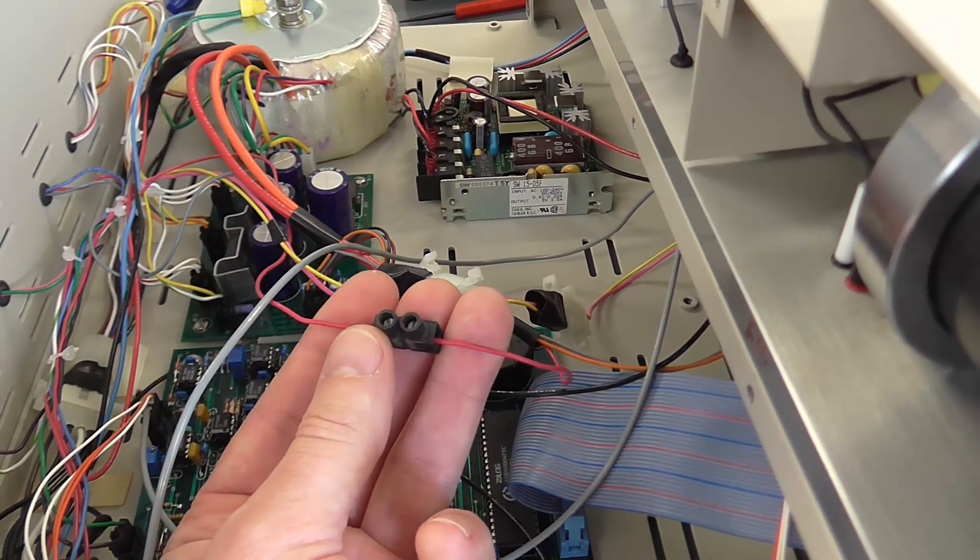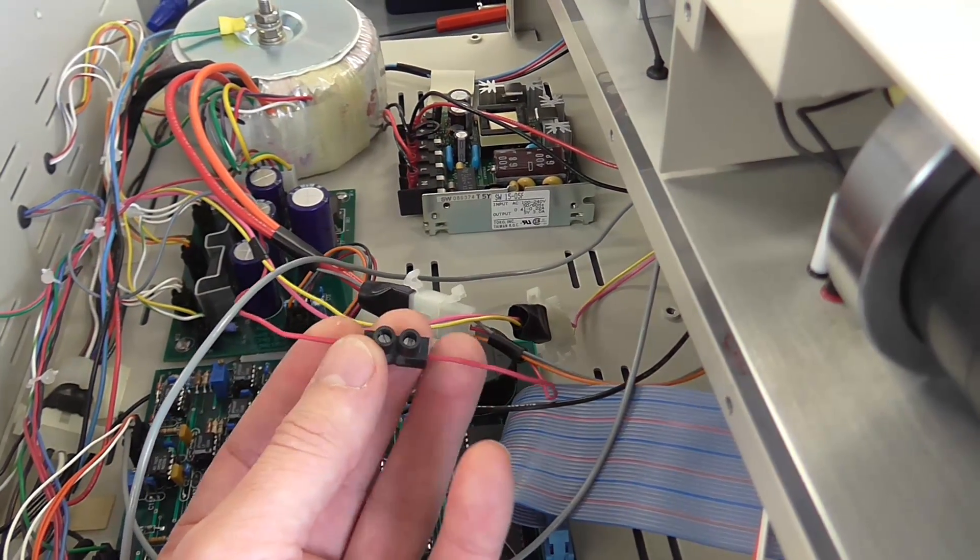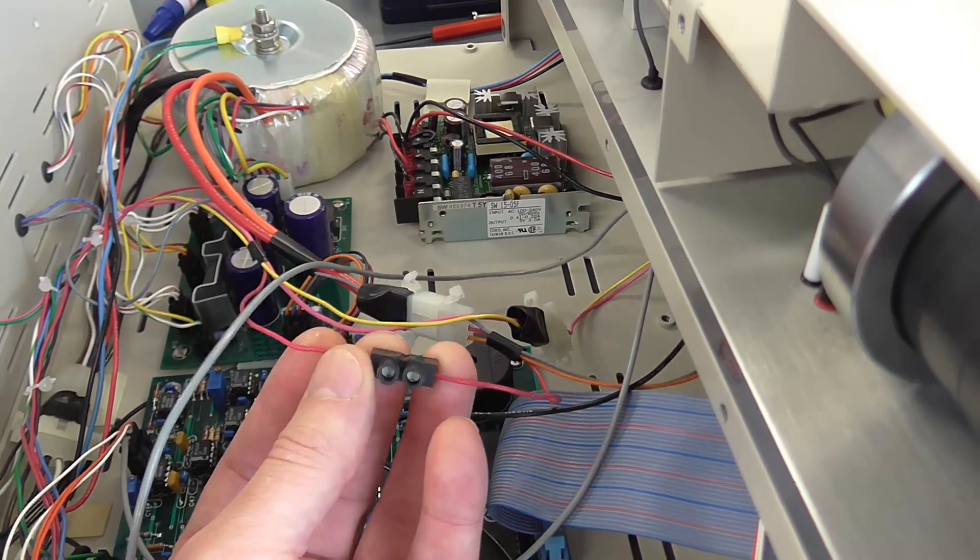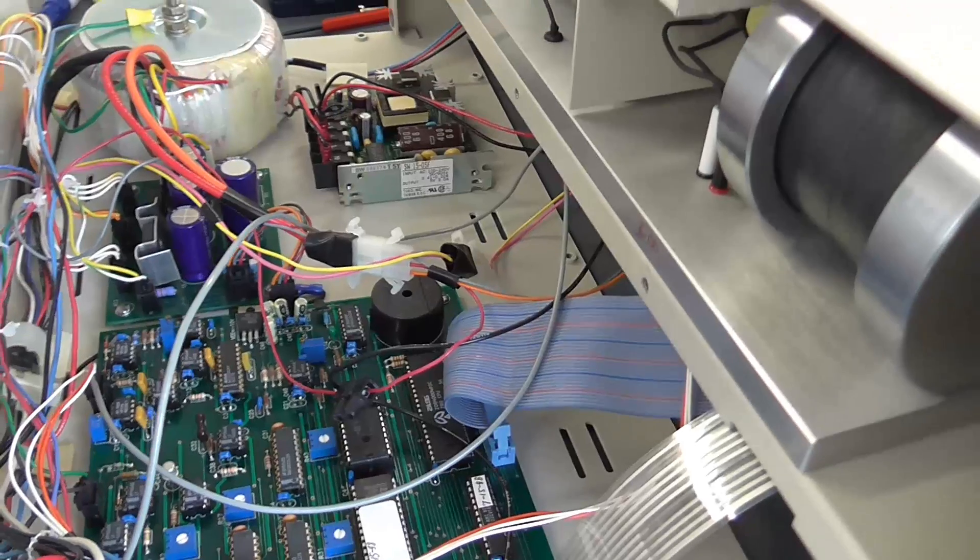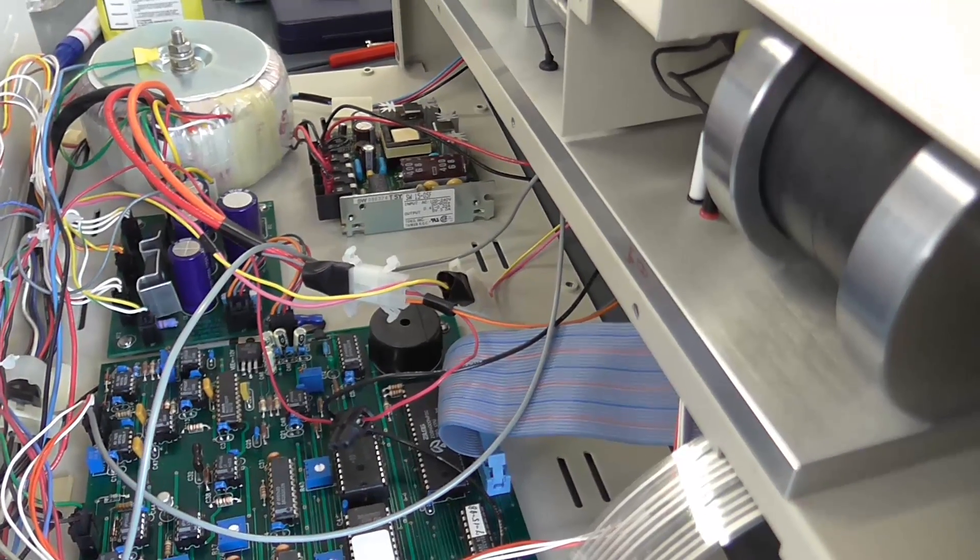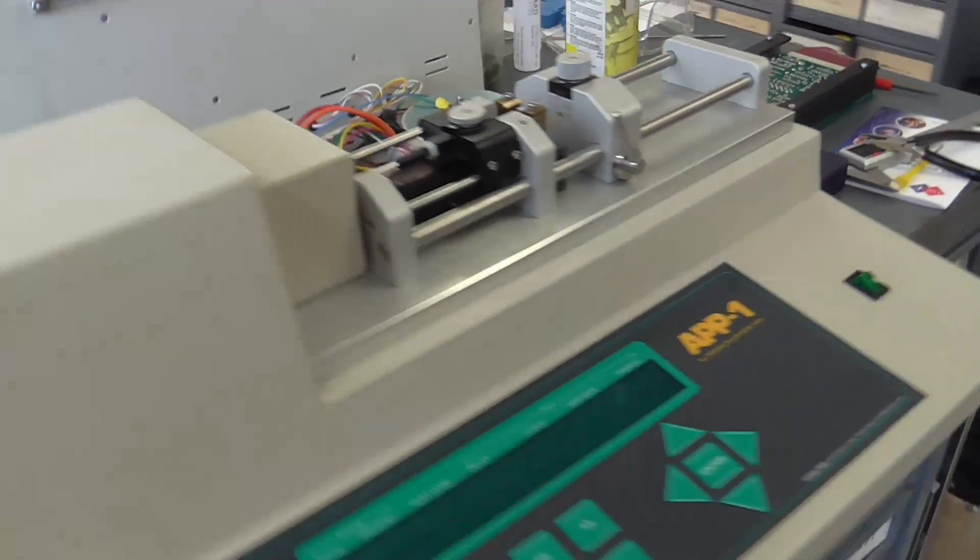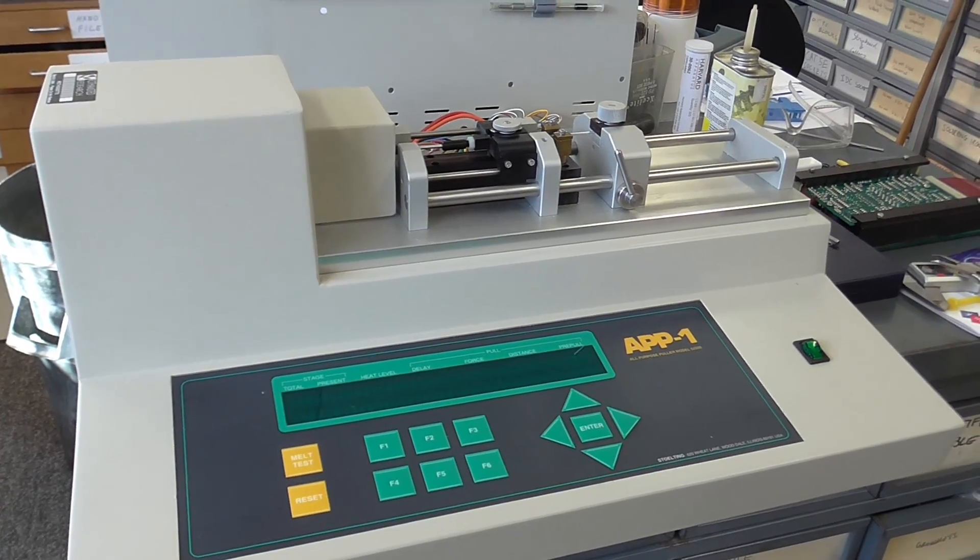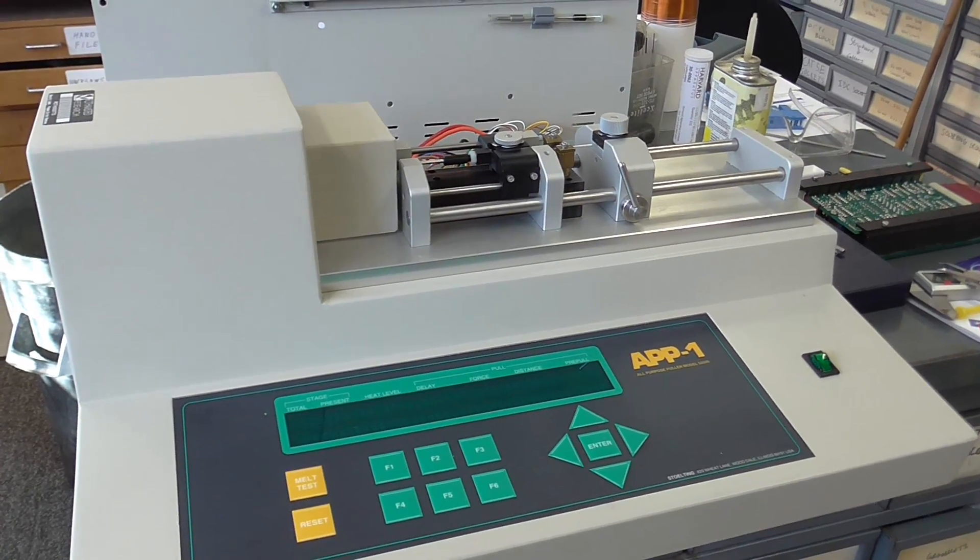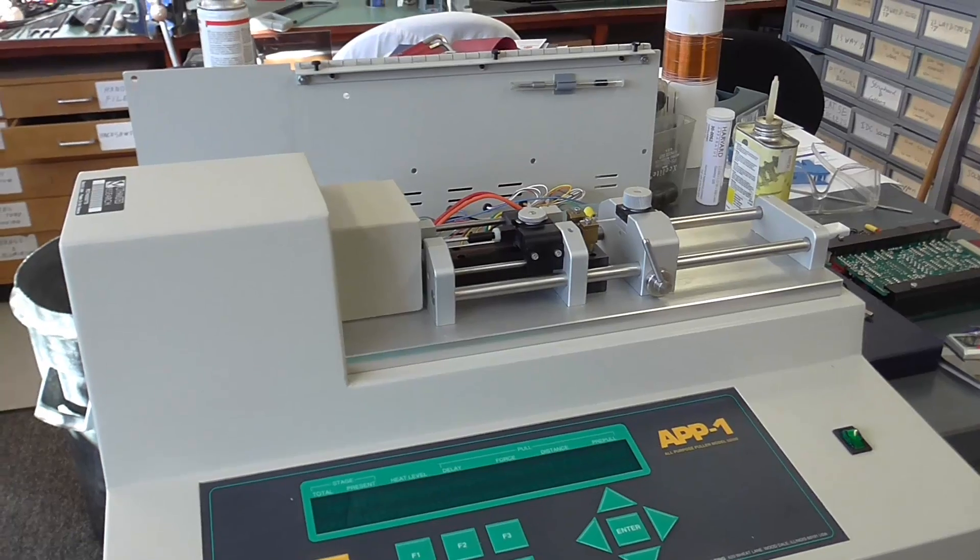So, on this occasion - I have repaired this instrument before - I've soldered this joint and sleeved it, but I've just put a terminal block in this time in case I have to take it apart again in the near future. One of these instruments is, I'm told, £4,000 to £5,000 to replace, so it's a good repair.